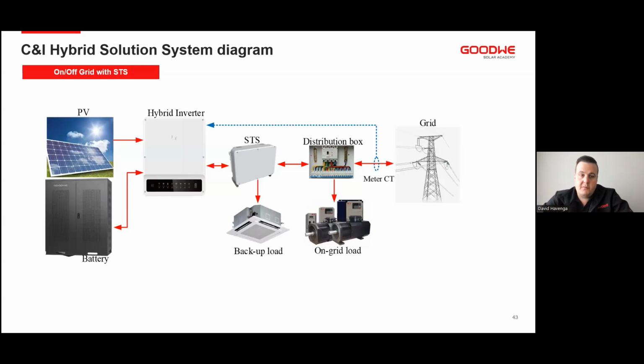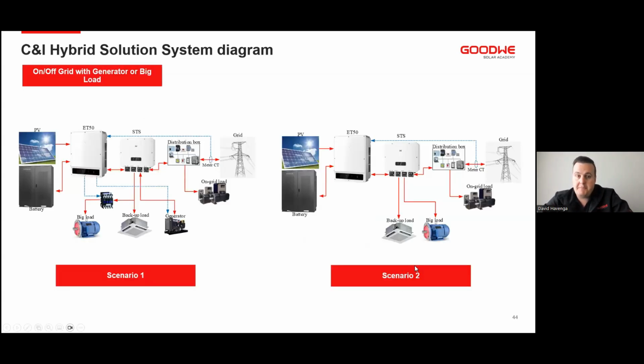An example here is the hybrid inverter, where we have our PVs, our batteries, and we have backup loads and on-grid loads. With the inverter, we also supply a smart meter for your metering on your meter side. However, our smart meter with this device does not come with CTs at all. You have to supply your own secondary 5 amp ratio CTs based on your customer's supply.